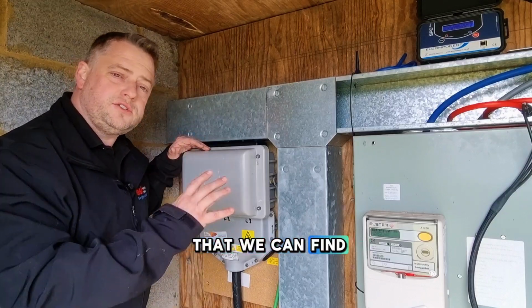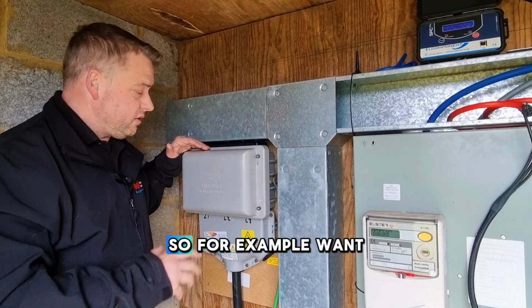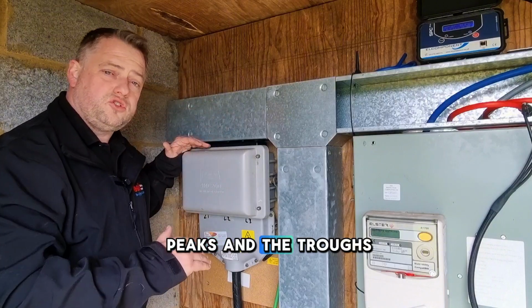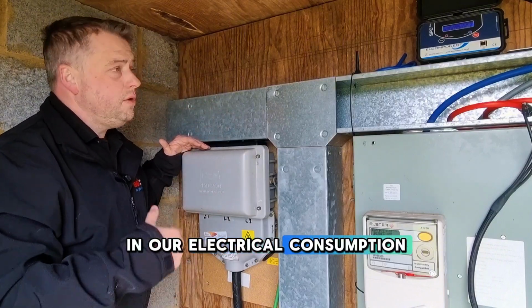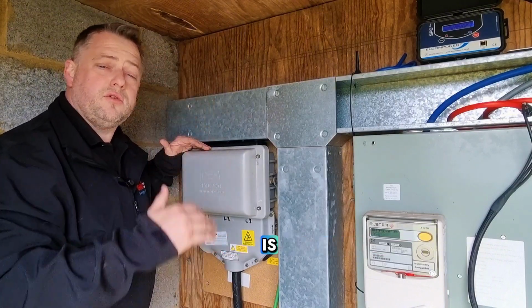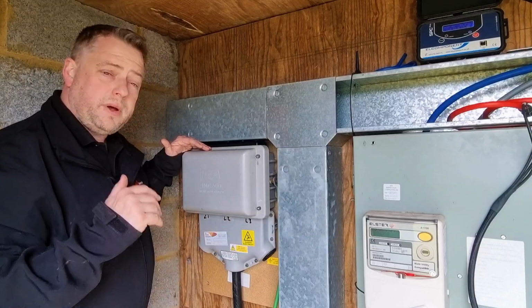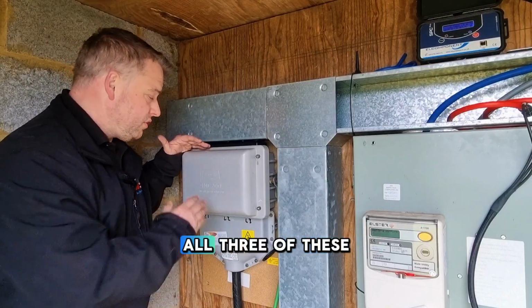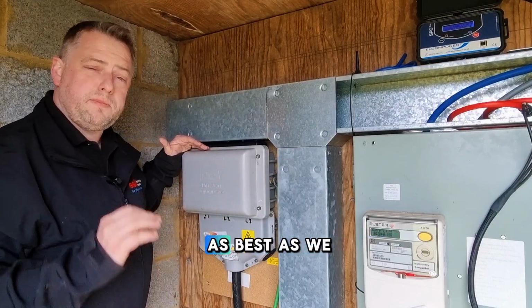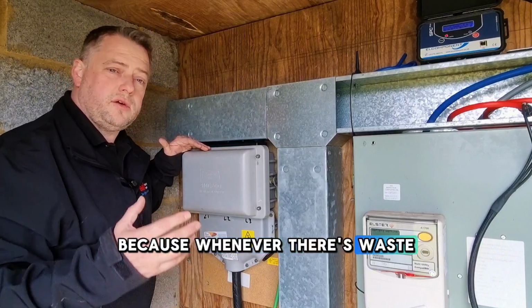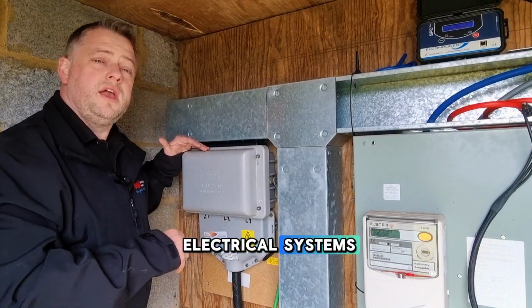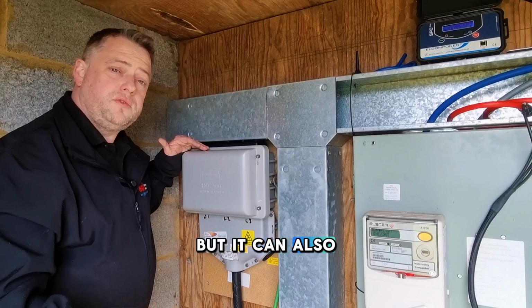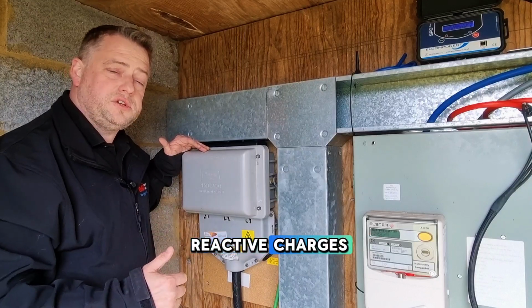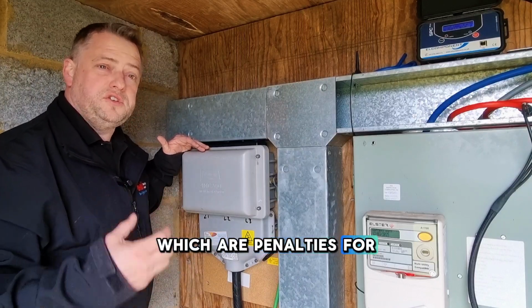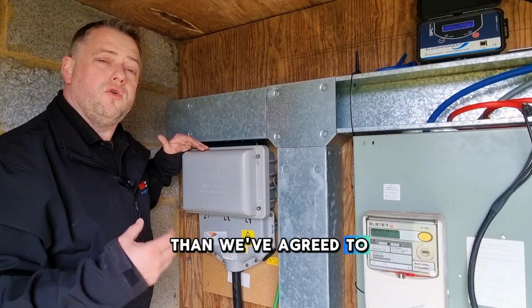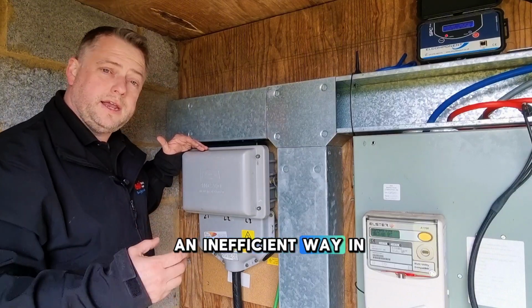There are some things we can find out during our survey that are really important. For example, we want to know when the peaks and troughs are in our electrical consumption, how high that peak is, and how low the minimum demand gets. But another important thing is that all three outgoing phases are balanced as best we can, because waste or inefficiency in our electrical systems can cause heat, but it can also cause problems with reactive charges, which are penalties for using more energy than we've agreed to or using it inefficiently.